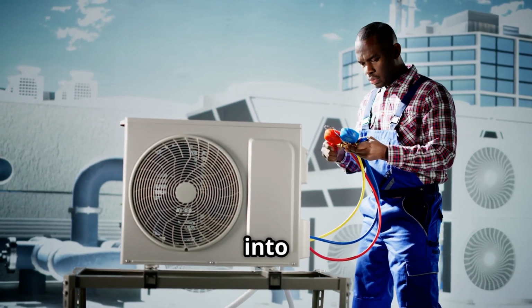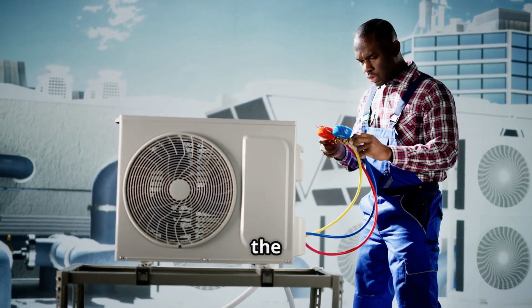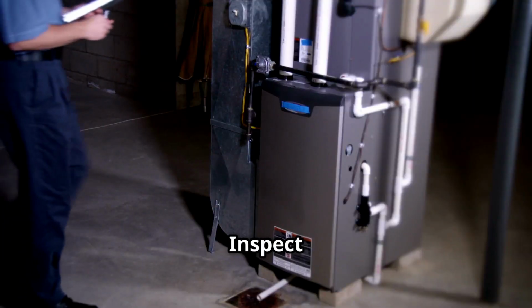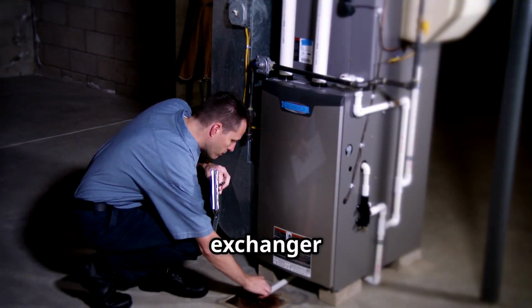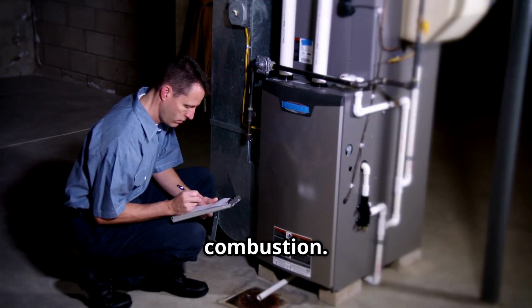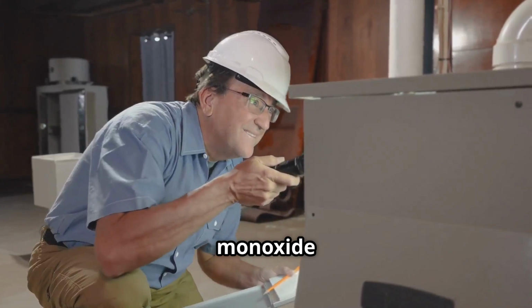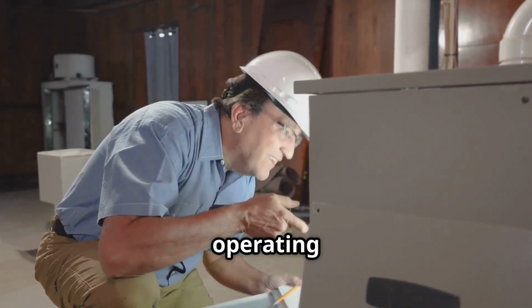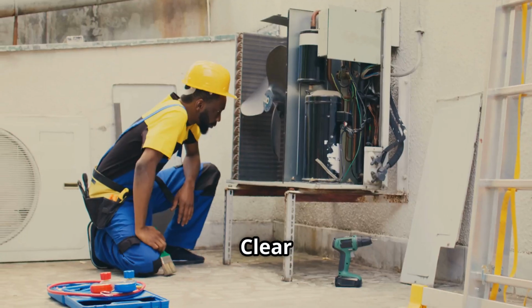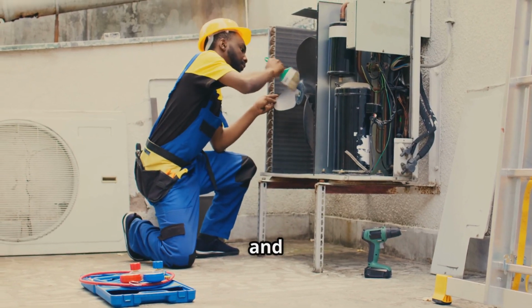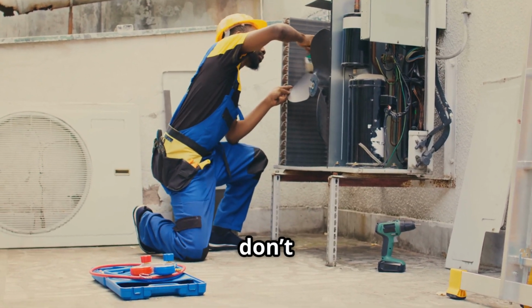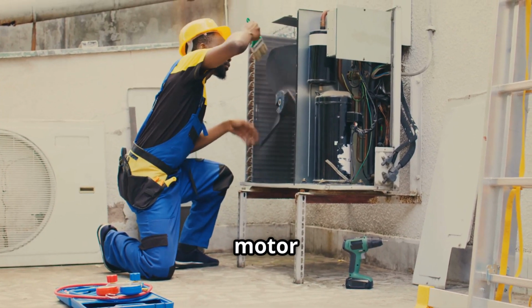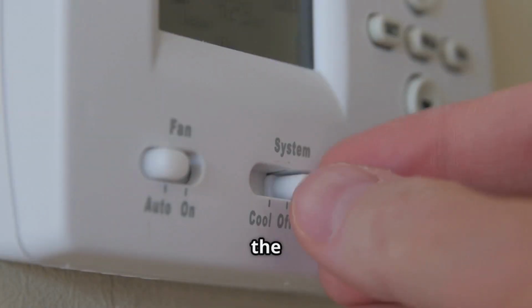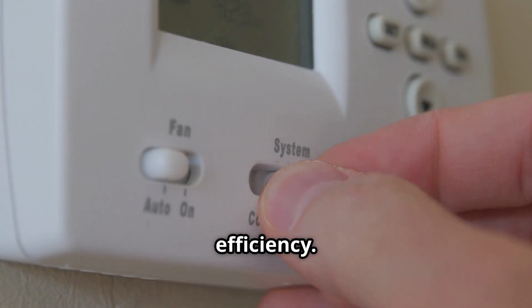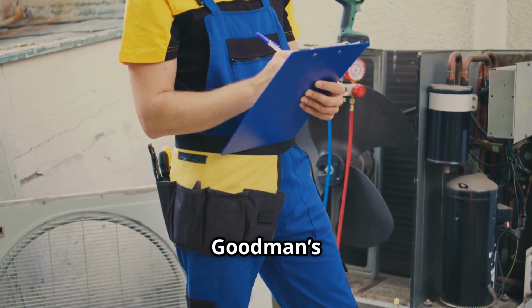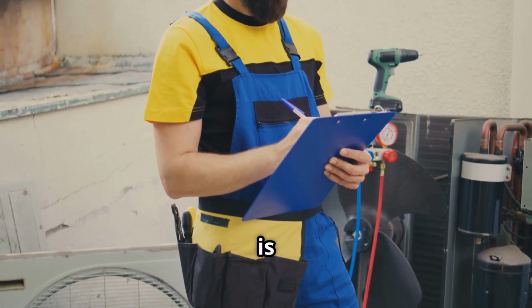Now, as we move into fall and winter, it's time to prepare for the heating season. Inspect those furnace burners and the heat exchanger for proper combustion. Test your carbon monoxide detector to ensure your gas furnace is operating safely. Clear any blockages in the flue and exhaust system, and don't forget to lubricate the blower motor bearings. Calibrate the thermostat to optimize heating efficiency. For more details, Goodman's Gas Furnace Inspection Guide is a great resource.